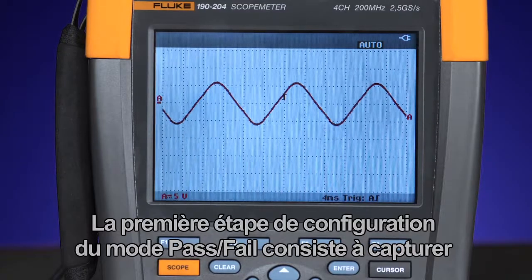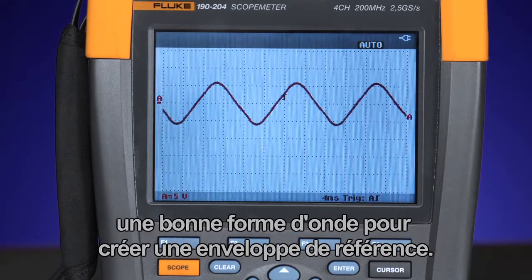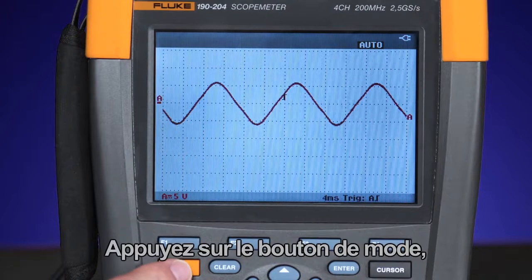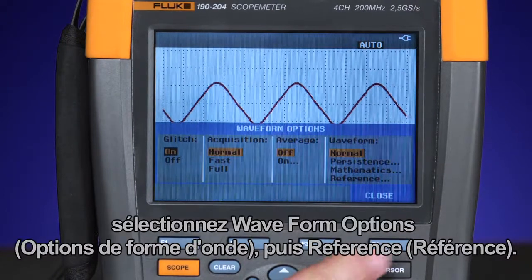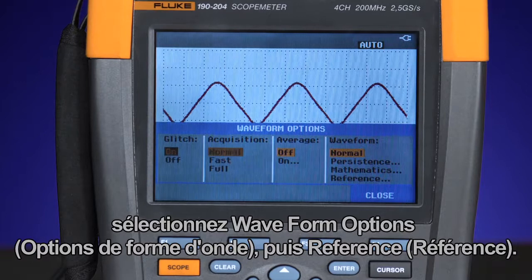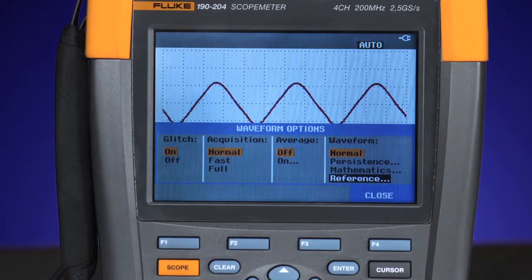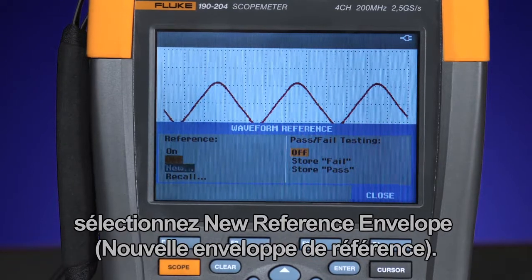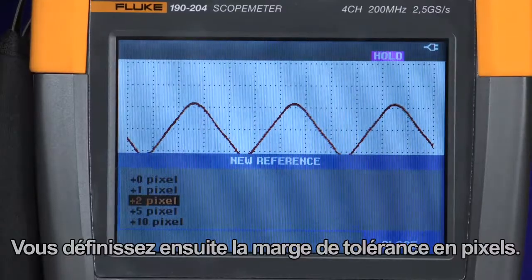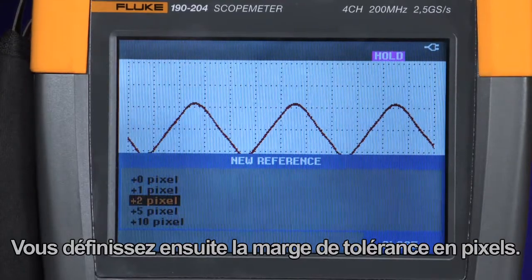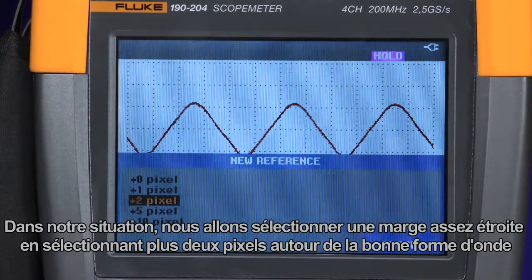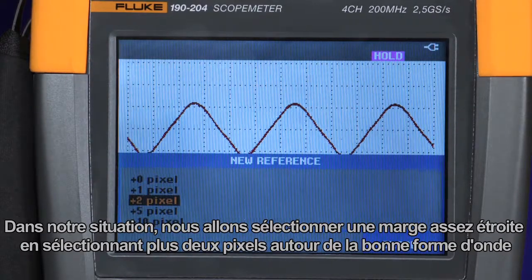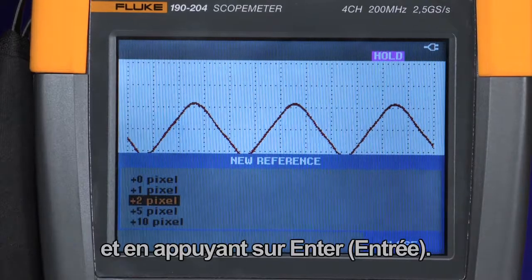The first step to set up pass-fail test mode is to capture the known good waveform and create a reference envelope. Press the scope mode, waveform options, and select reference. In the waveform reference menu, choose a new reference envelope. Here is where you define the window of tolerance by the number of pixels. In this instance, we'll choose a relatively tight window by selecting plus 2 pixels around the known good waveform, then pressing enter.